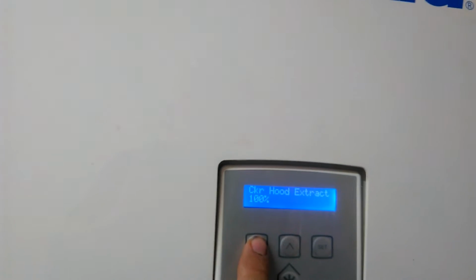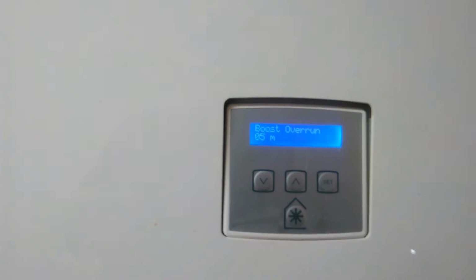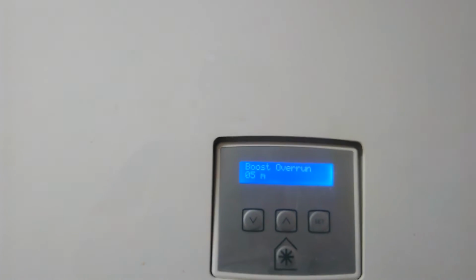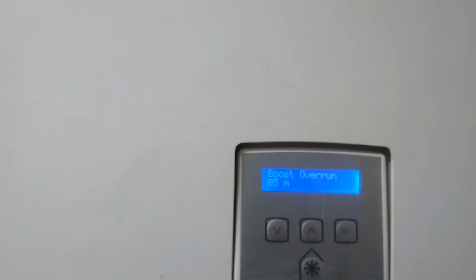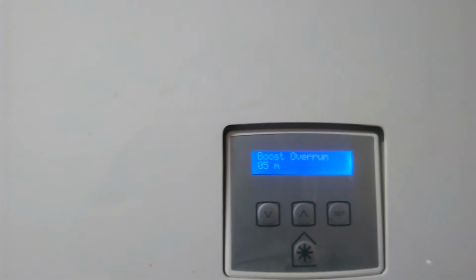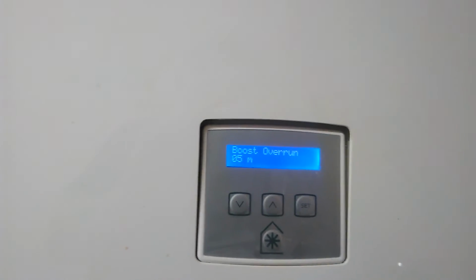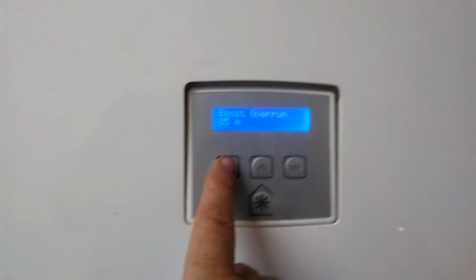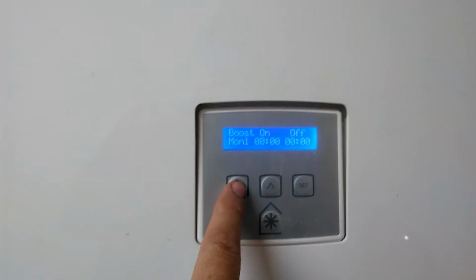Cooker hood extract. This unit isn't attached to a cooker hood. Most of the time, we just ignore that in an airtight house anyway. Okay, we've got boost overrun. I usually set this to 5 minutes just so people can get to sleep at night in case the unit gets put into boost mode by accident. Let's say if they've got a switch attached to the system as well, because you can put mechanical switches to switch this unit into boost mode too. Boost delay, don't worry about that.